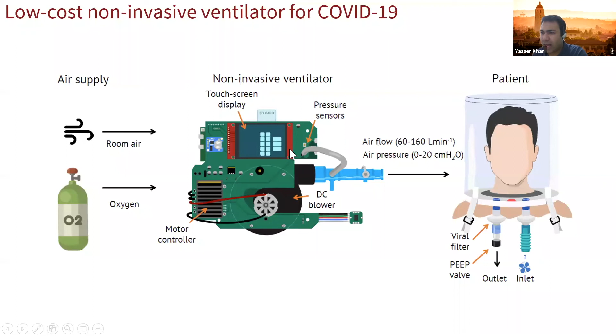Yeah. All right. So here you can see we have the air supply. You can use room air and also oxygen. And these two air sources will come to the ventilator. And then this can actually provide airflow of 60 to 160 liters per minute and air pressure of 0 to 20 centimeters of water. We basically designed this in 6 weeks.